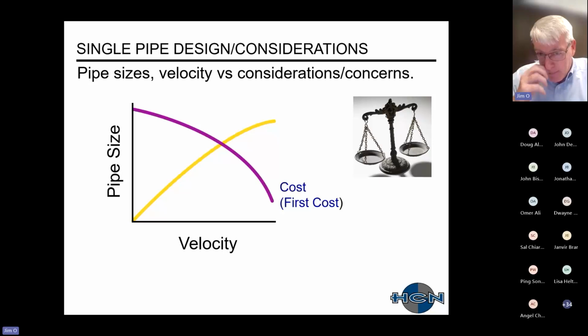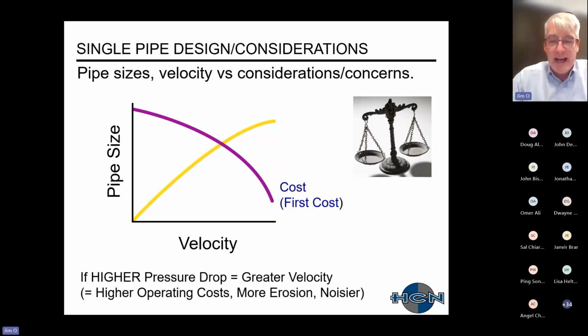You're trying to find a happy balance. You don't want your piping to be too big, on the left there, because your velocity is probably lower than it should be, but you're adding additional first cost. But then you don't want to go the other route, very far to the left on this graph, where you're really restricting or putting in much smaller pipes than you should have. What will happen is that will create a greater velocity, as shown in the yellow there, and then higher pressure drop turns into higher operating cost, causes noisier systems, and also creates more erosion inside of your piping systems, et cetera.